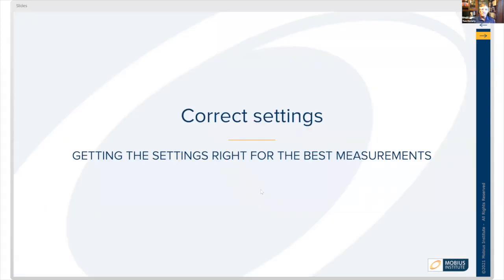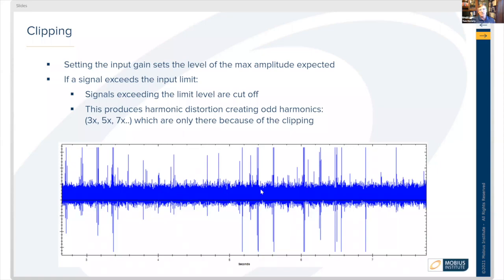Let's talk about correct settings. We want to get the settings right for the best measurements. The first concern is clipping, which occurs when the range of amplitude you're trying to collect data on is less than the amplitude of the sound actually being generated. Setting the input gain sets the level to the maximum amplitude expected. If a signal exceeds that limit, the signals start exceeding the range of your scale.